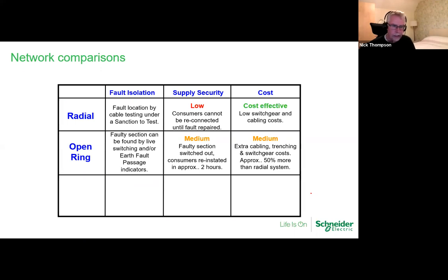They've obviously got to get to site from wherever they are, and then they've got to figure out what's been going on. DNOs, they're going to be doing that remotely. They're going to be monitoring it all the time. Their control rooms are manned 24/7, irrespective of weather, irrespective of whether it's a holiday or not. The supply stays on, and they're mandated legally to restore it within 3 minutes. Otherwise, they are going to get fined by the regulator, and those fines could ramp up into millions of pounds.